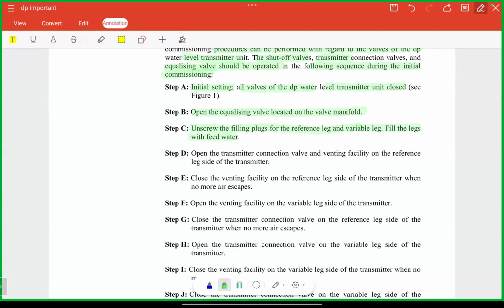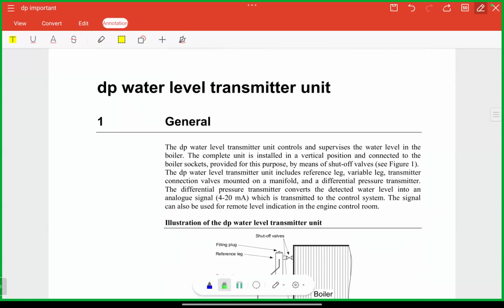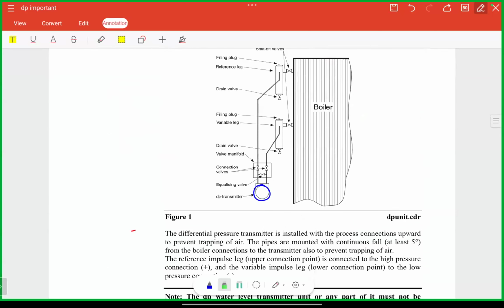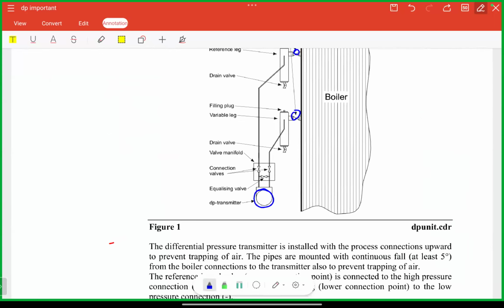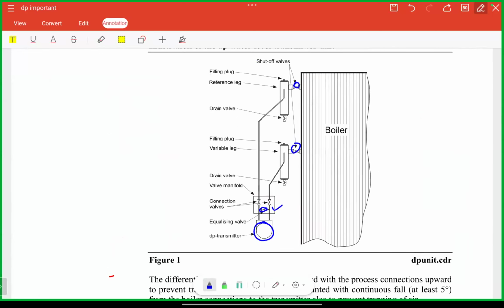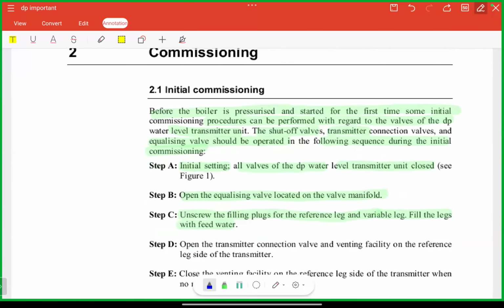Open the equalizing valve, open the filling plugs on the top of your condensing pot. Initial setting: all valves of the DP water level transmitter unit closed. That means on the valve manifold, on the steam side and on the water side, this isolation valve, keep it closed. Open this equalizing valve. Open the filling plug and fill fresh water on both sides of the DP transmitter.